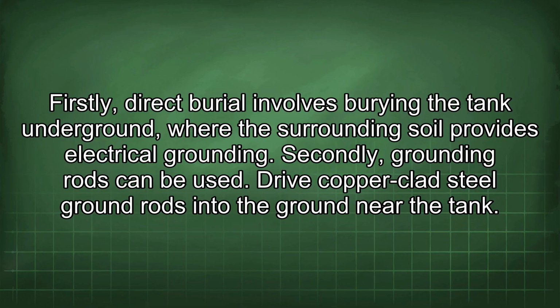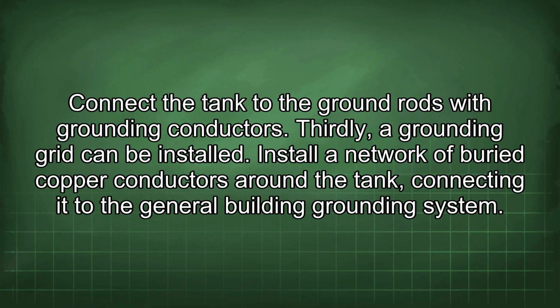Secondly, grounding rods can be used. Drive copper-clad steel ground rods into the ground near the tank. Connect the tank to the ground rods with grounding conductors. Thirdly, a grounding grid can be installed. Install a network of buried copper conductors around the tank, connecting it to the general building grounding system.